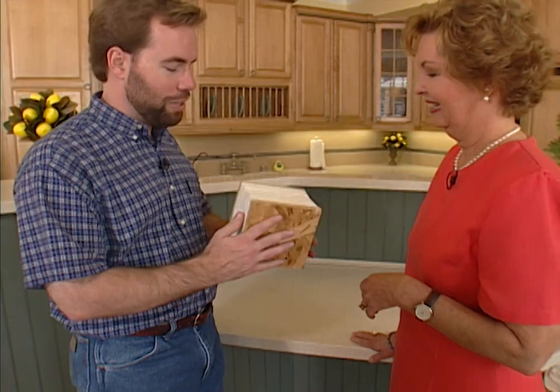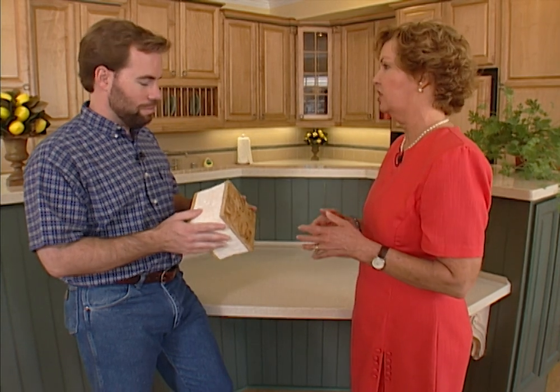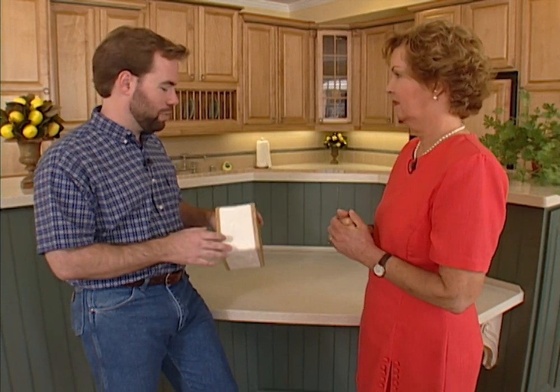So you got foam in between two pieces of wood, and that made up your house and your roof. Exactly. That's it. It's very tight, and it's so tight that it has no infiltration. Most houses are ventilated by leaks. This house is ventilated by an air-to-air heat exchanger that saves the heating or cooling energy while it replaces the stale air with fresh air at an exact prescribed number of 0.3 air changes per hour. So there's no drafts throughout the house. Right. Low utility bills. I like that.